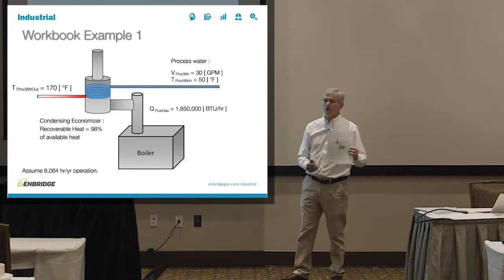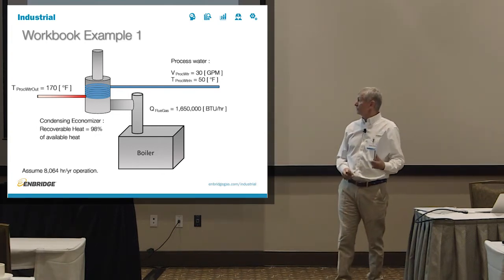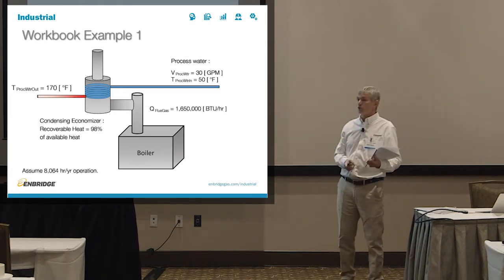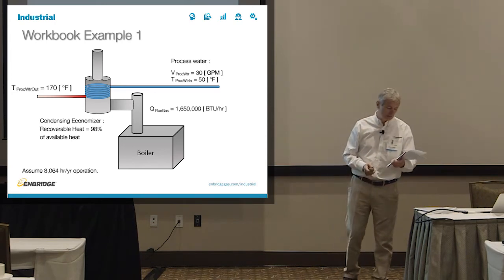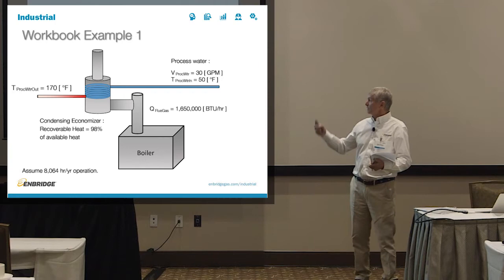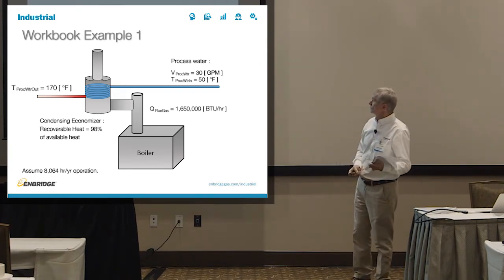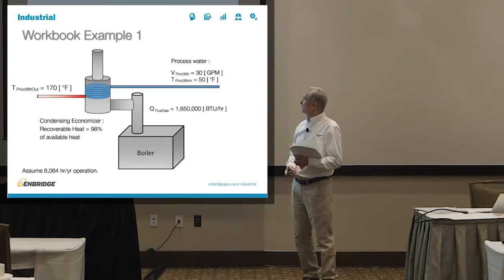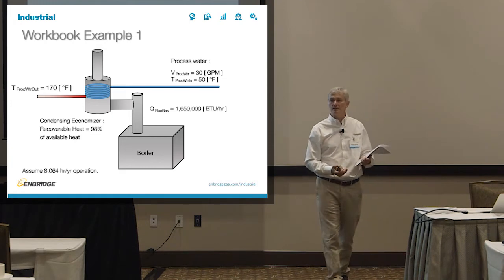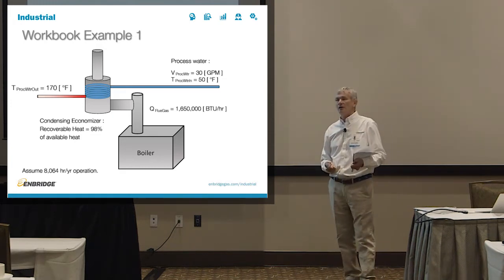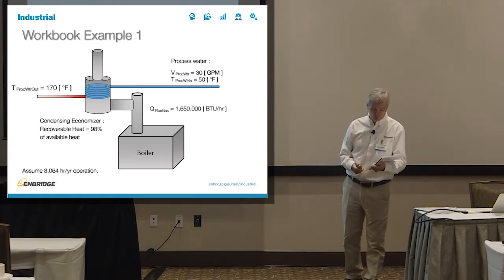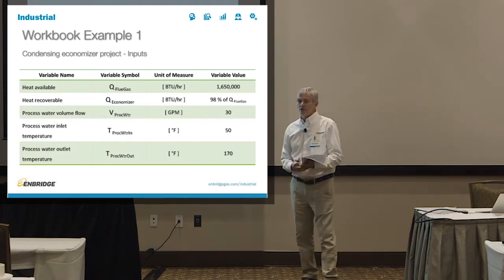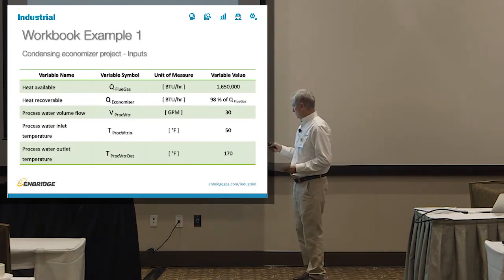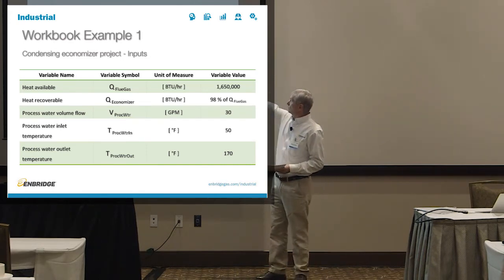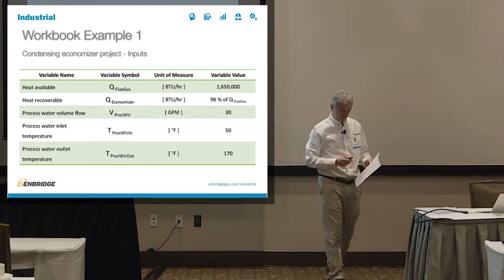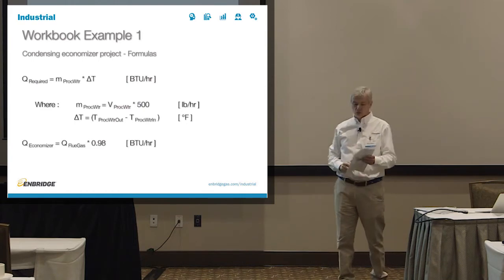So we will install a condensing economizer onto the boiler. We will say that we already determined that the boiler flue gas gives us energy of 1.65 million BTUs per hour. We'll say that the condensing economizer can recover 98% of that heat, which is a typical number. And we will say that we process about 30 GPM of water, process water coming into the facility at 50 degrees F, which is typical city water. And we want to get up to 170 degrees F at the exit of the condensing economizer. So this summarizes our inputs. If you look at the numbers here, you will see the symbol in the middle, the units of measure, and the values. And the idea is we're going to put those into the formulas on the next page.